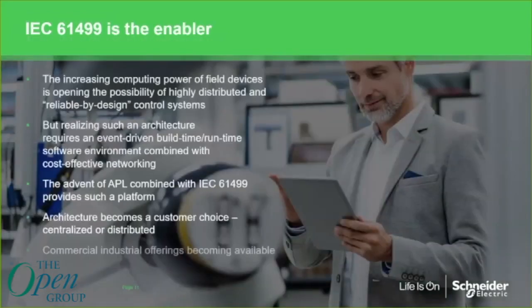61499 allows you to take advantage of the increasing field device power and opens up a highly distributed architecture that is quite reliable by design. You don't have to work on anything fancy. If a device fails, you lose the one signal. You don't lose anything else. Realizing such an architecture requires an event-driven runtime, and that's what 61499 is all about. It allows you to deploy to those distributed devices.